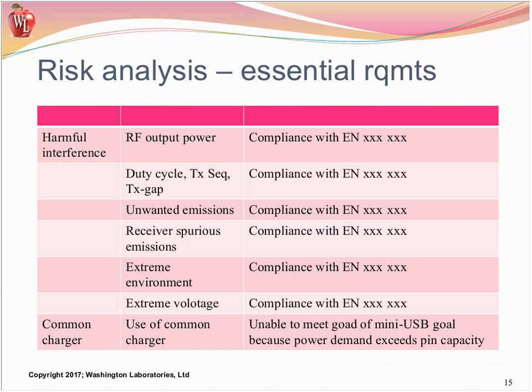If you're trying to make a very short table on how you do it, that one area may be referring to section 6.4 for the detailed explanation of why you have to use what you do. You may declare it is subject to approval instead of does not meet the requirement. It's an indicator that, yeah, it's subject to approval. We're waiting on a response, and we believe it's going to come out, versus, hey, this thing fails, accept it anyway. I don't think that's going to get a lot of use, but your positive approach is that this is pending approval. And once the approval happens, you update your risk analysis to show the approval. This deviation from certain standard was approved by so-and-so, whatever. And that covers you until the standard update happens. I hope that explained enough.